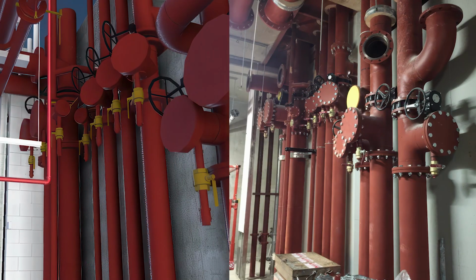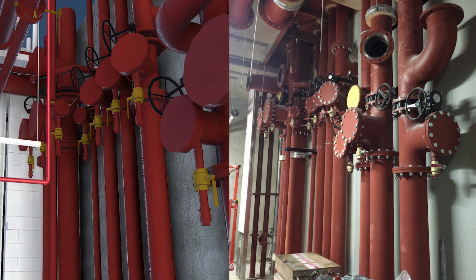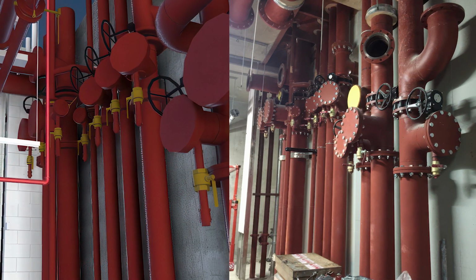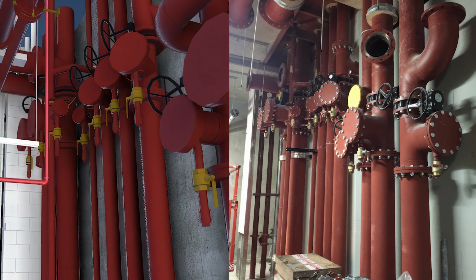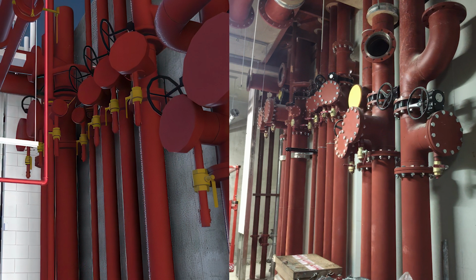While we're on the subject of the riser, there was the anchor point in the basement. Yeah, that was a bit of a faux pas. If I remember right, it wasn't so much the anchor, it was the dirt pocket at the bottom that was the problem. There was a branch, a dirt pocket with the IV and everything else, I think possibly a 50 mil stub off with an IV drain. So basically what they said was, we'll flange all that, have a false piece of steel pipe down to the actual basement floor level, and use that as an anchor point for the expansion of the riser.